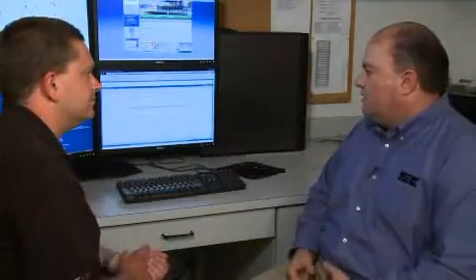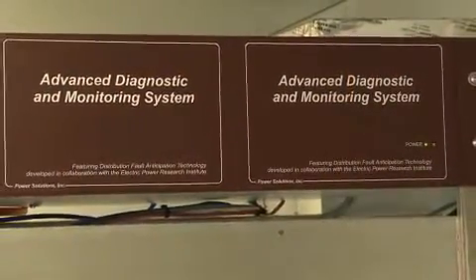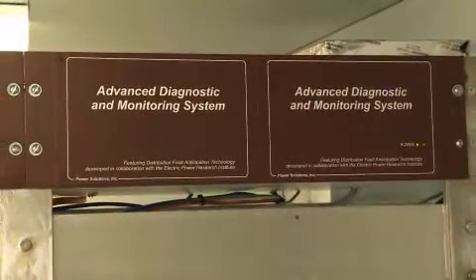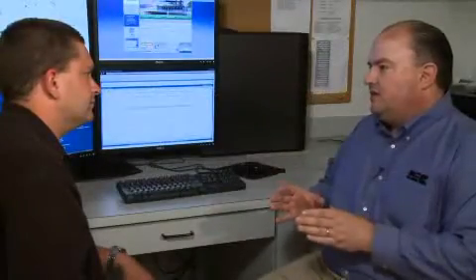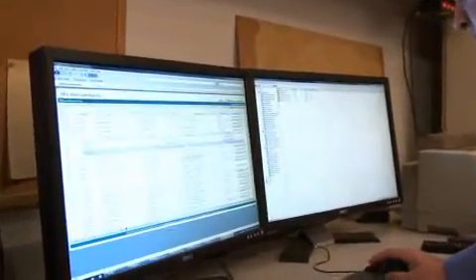What sort of hardware and software makes up the DFA system? The DFA box itself is deployed on one feeder — that's the way we're deployed, one box per feeder. We're monitoring bus PTs and CTs, currents and voltages. The DFA captures the waveforms and then inside the box itself it sorts through them, decides what each event is, and it picks the ones that it determines we want to know about and sends them to us and displays them on the website.